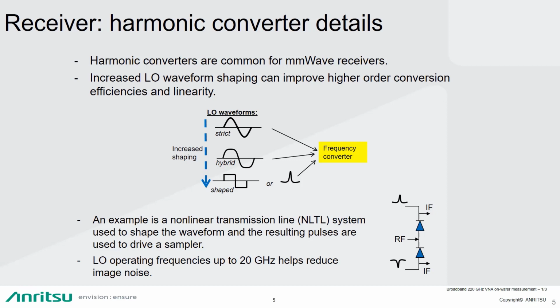And so in the VectorStar system, what we use is nonlinear transmission line technology to shape the waveform, and the resulting pulses are then used to drive the harmonic sampler. So it's the NLTL modules, the millimeter wave modules, using the triggering mechanisms for the downconversions within the module and close to the test port. Another aspect for improvement of performance is to operate the LO source at higher frequencies, and so using frequencies up to 20 gigahertz will help reduce the image noise.